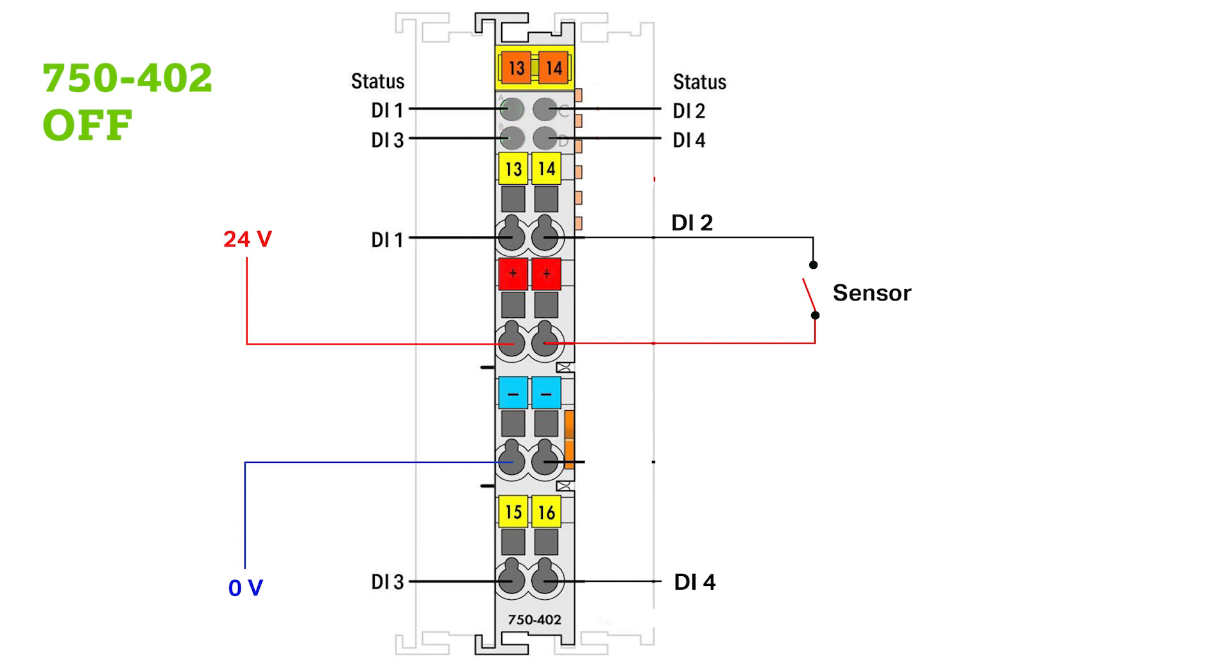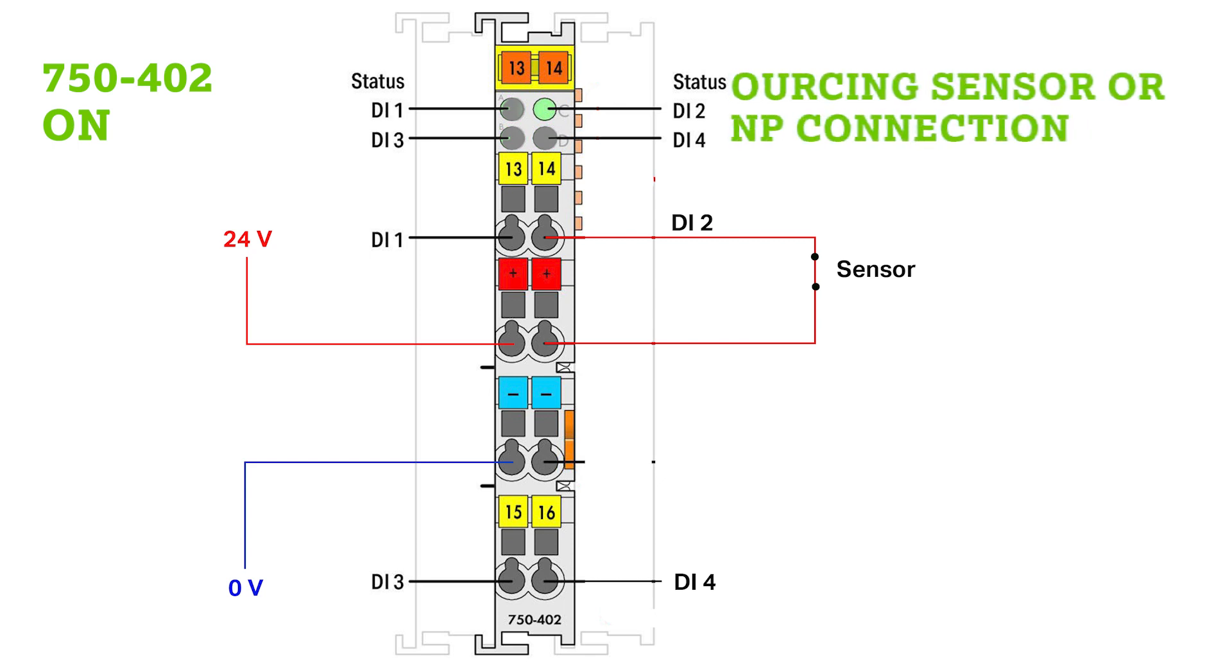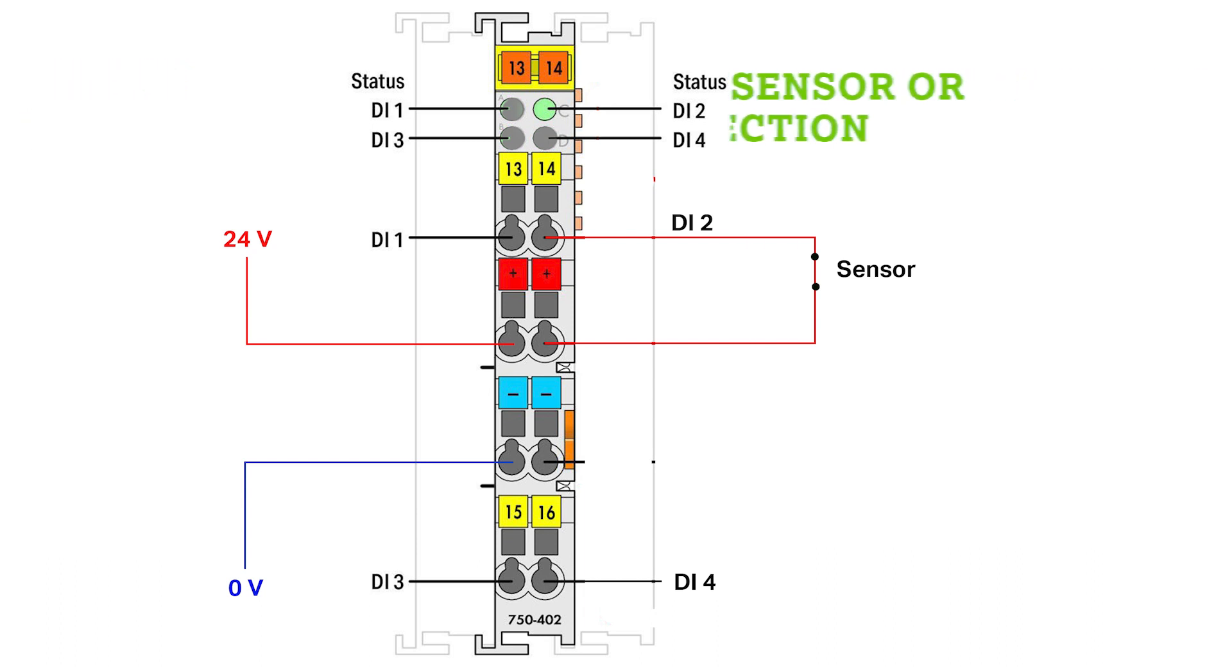Now let's look at digital input modules. WAGO's high side switching input module, the 750-402 for example, is expecting a 24V signal at the input to be considered an ON value. That 24V would be considered as a sourcing sensor and a PNP connection.